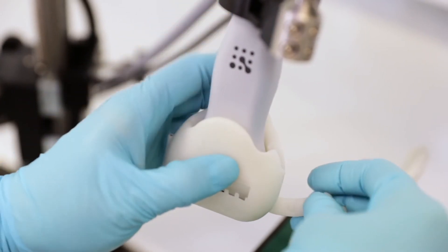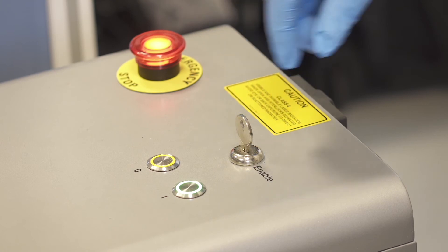It's really easy to set up. You simply fit the jacket onto the transducer probe and then choose the right optical fiber for your application to slide into the jacket. On startup, you can customize the intuitive Vivo LaserX software interface.